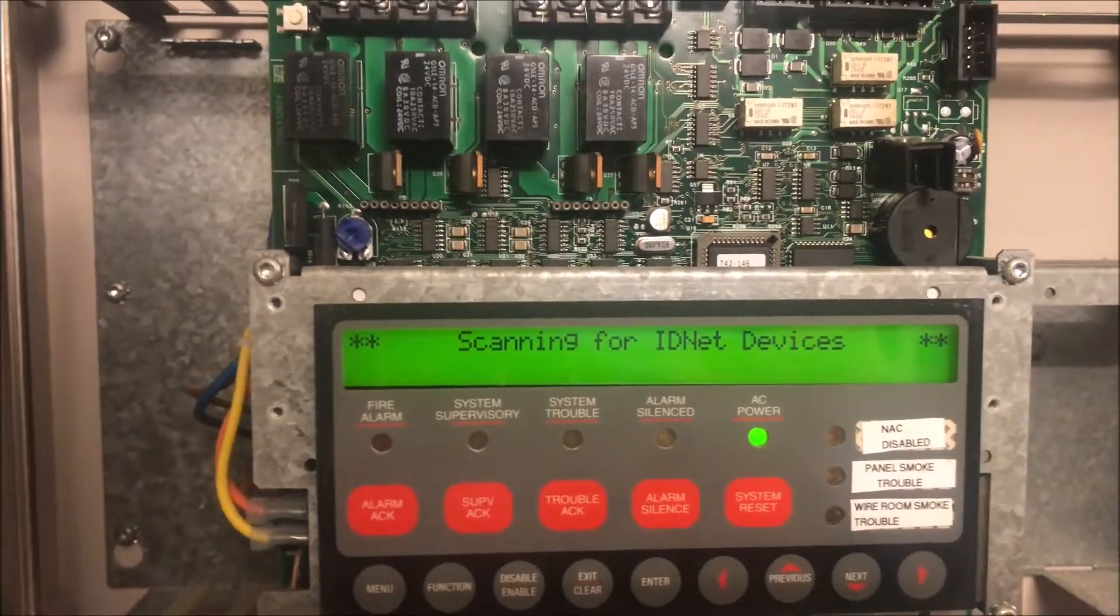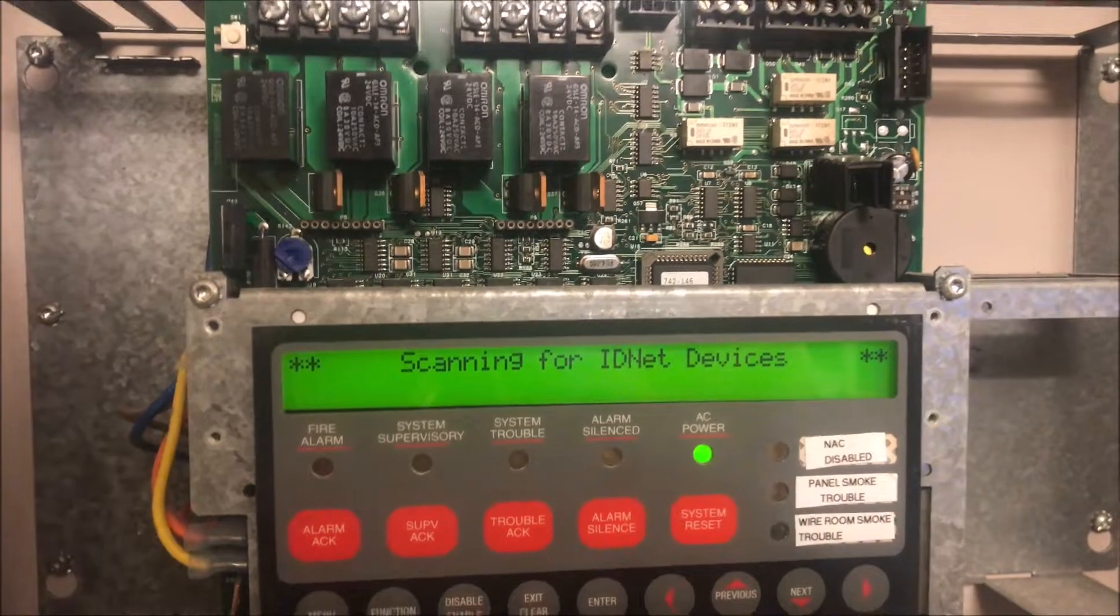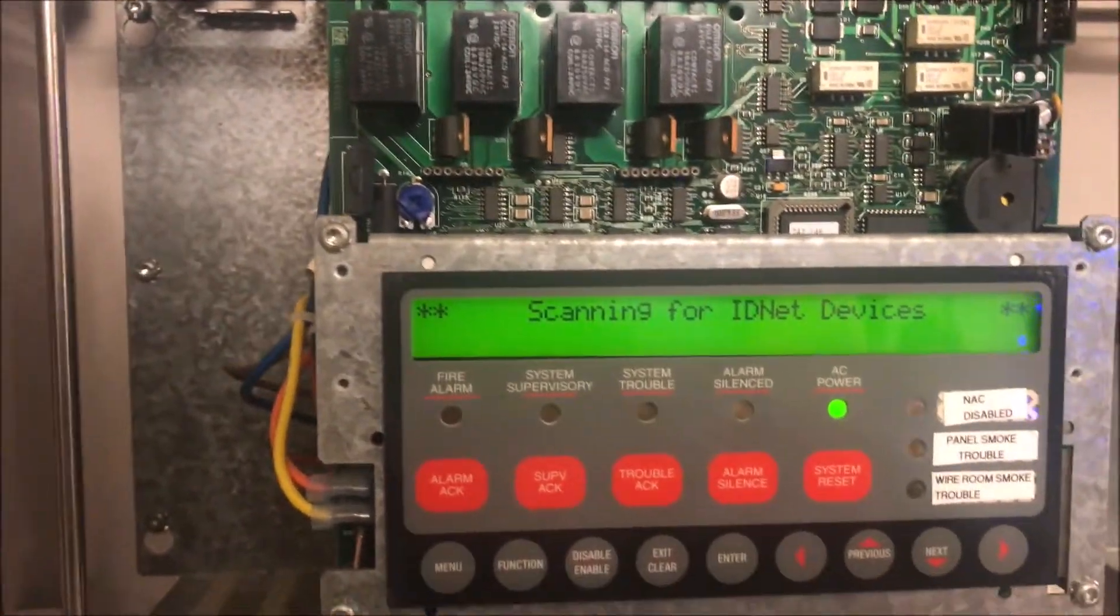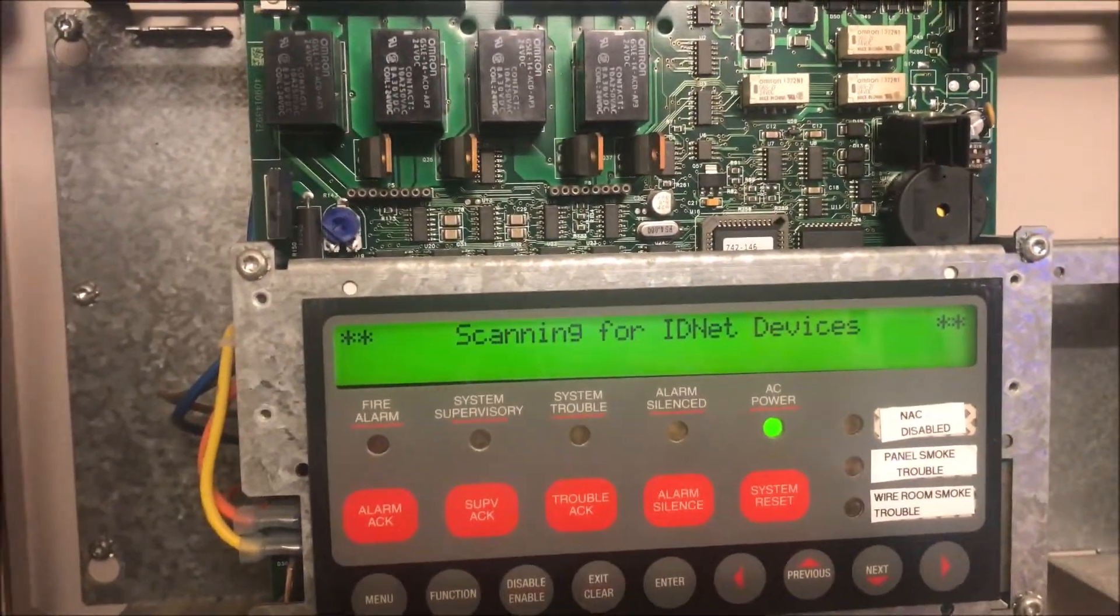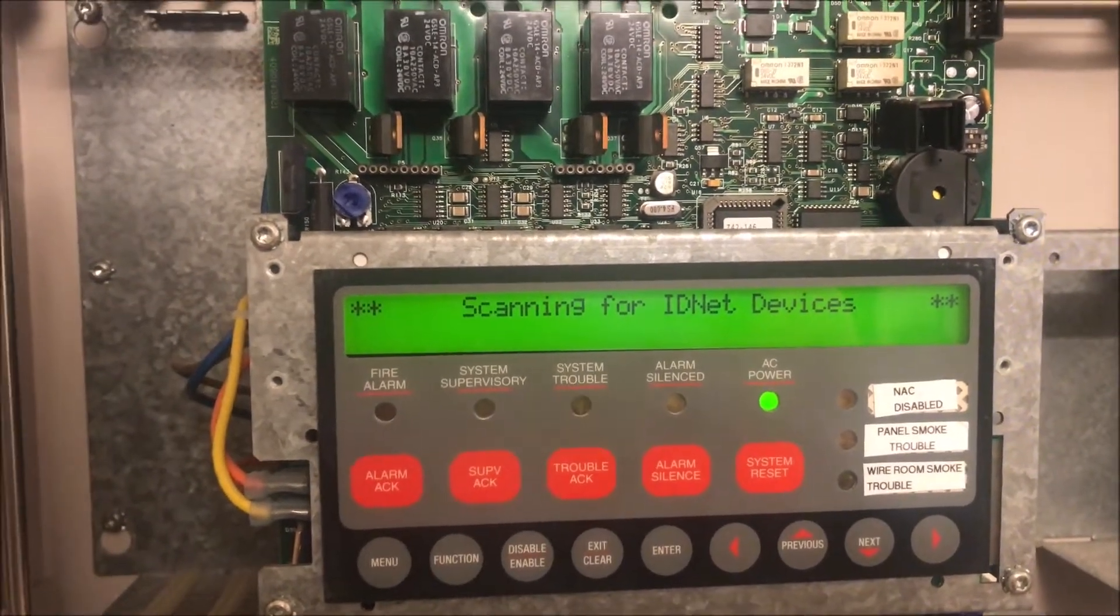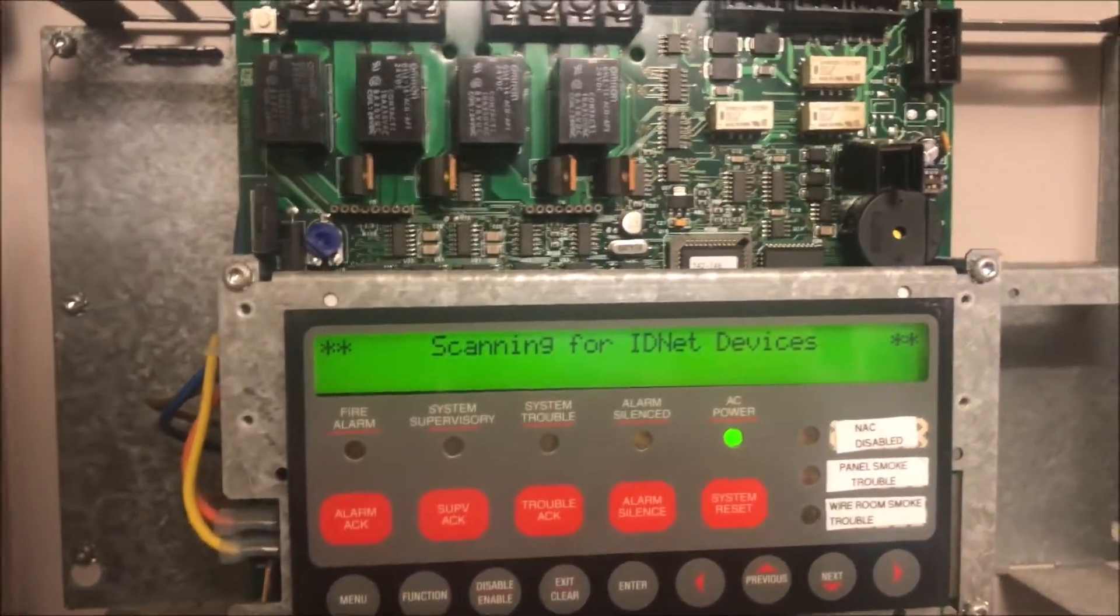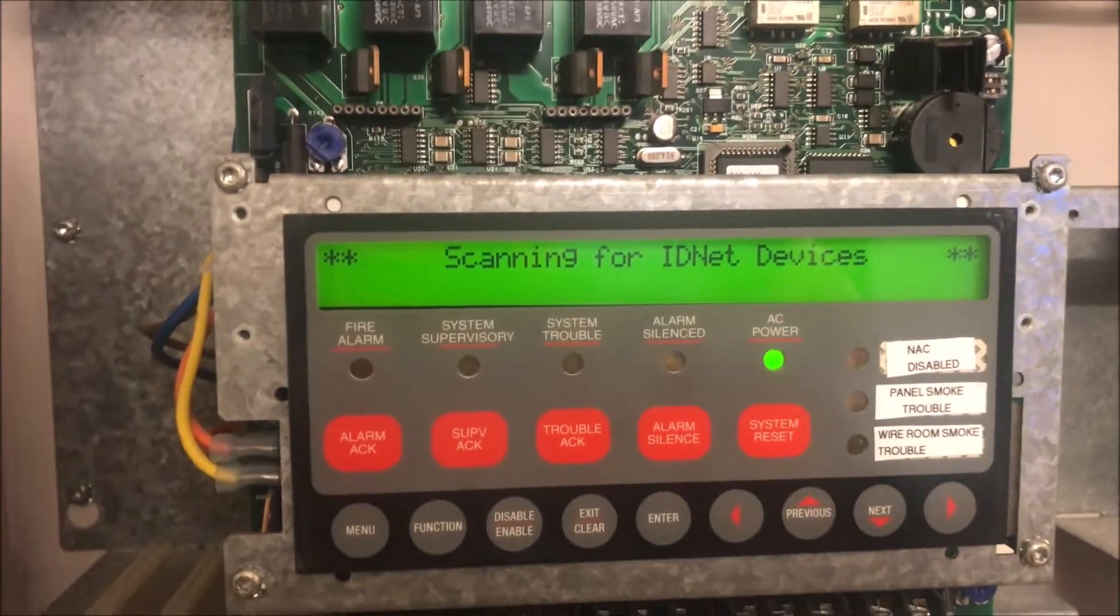These are things like pull stations, smoke detectors, anything basically with an address that's on node one or node two. But because this is a 4010, we only have one node, so everything's going to be on node one. Right now it is checking the entire SLC loop for devices.